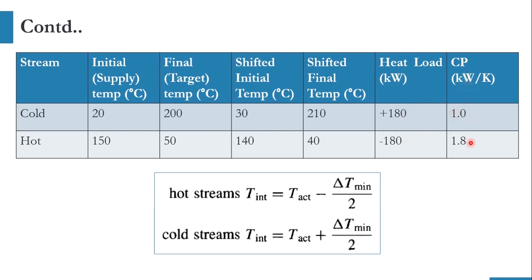CP values are given as 1 and 1.8. For the hot stream shifted interval, we subtract delta T minimum over 2. Since delta T minimum is 20°C, that gives 10°C. So 150 minus 10 equals 140, and 50 minus 10 equals 40. For the cold stream we add: 20 plus 10 equals 30, and 200 plus 10 equals 210. This completes the first table.